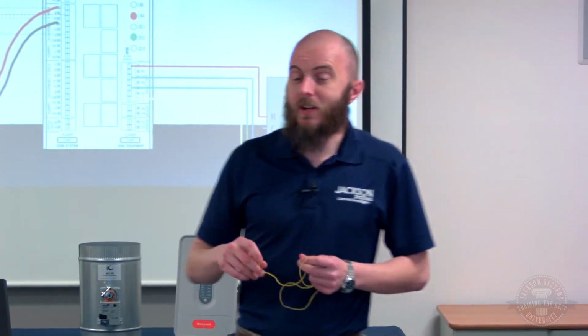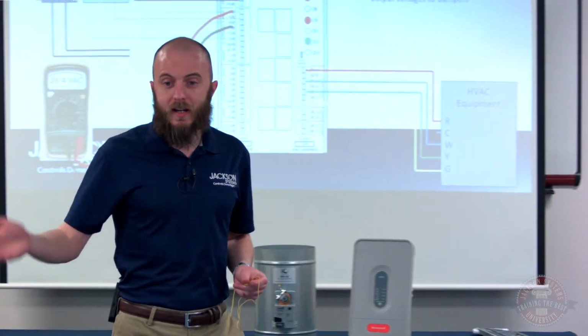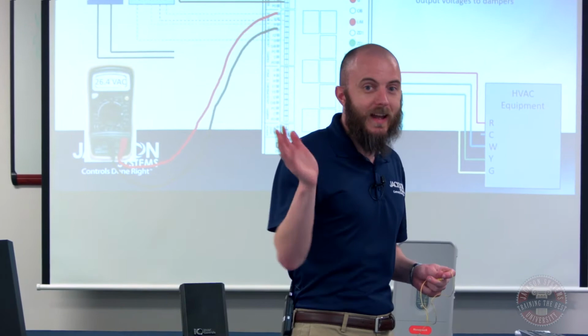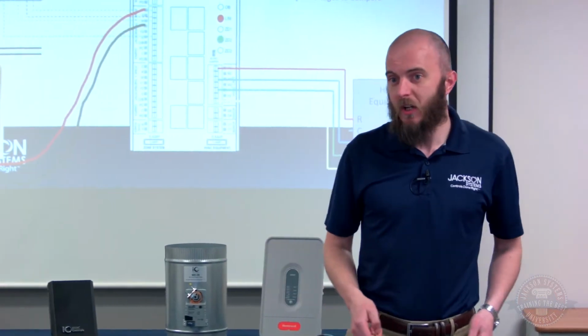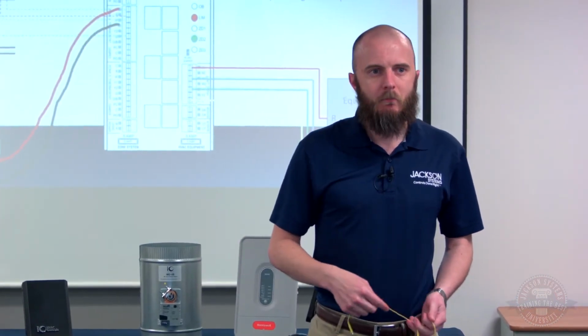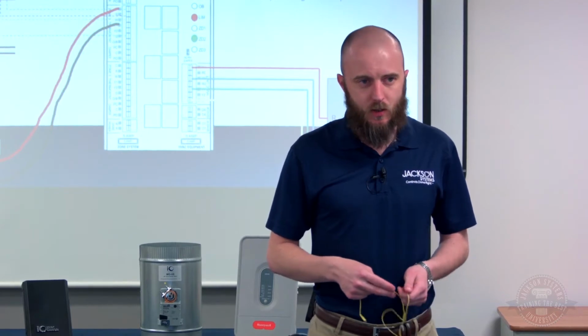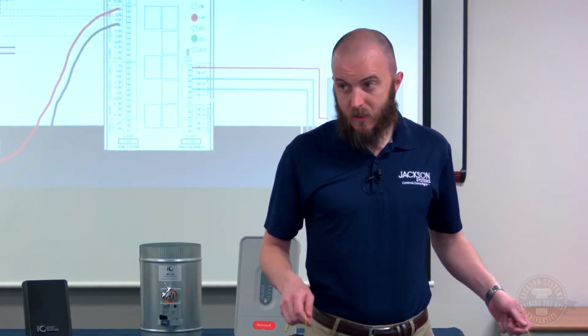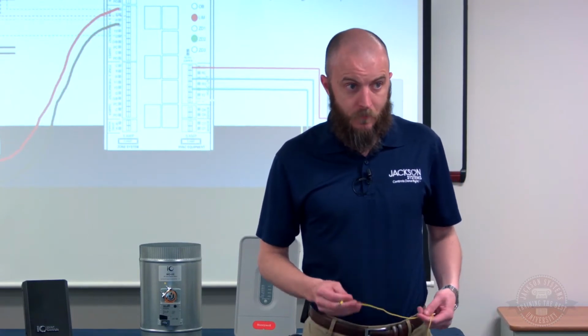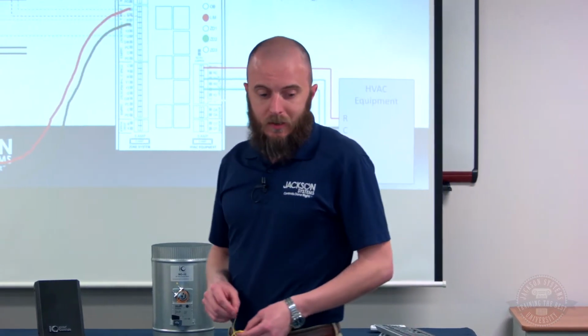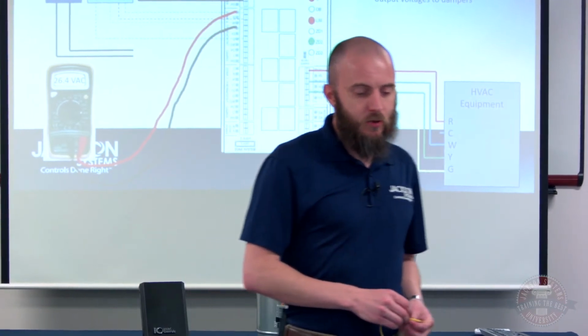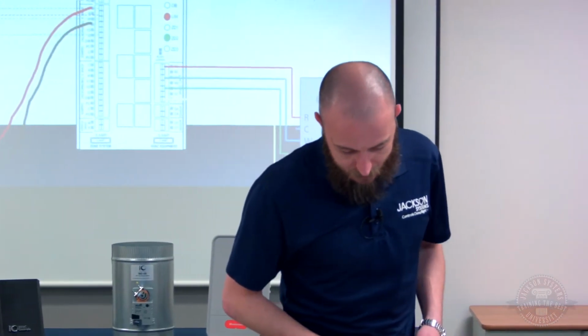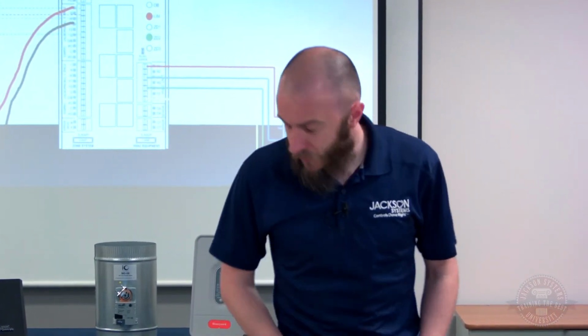The reason we started doing this training is because not too long ago, a year ago, I'd say 75% of the zone panels that were returned to us as defective under warranty, we tested them and there's nothing wrong with them at all. Thorough testing and troubleshooting of zone panels can save you a lot of time and trouble in the field.